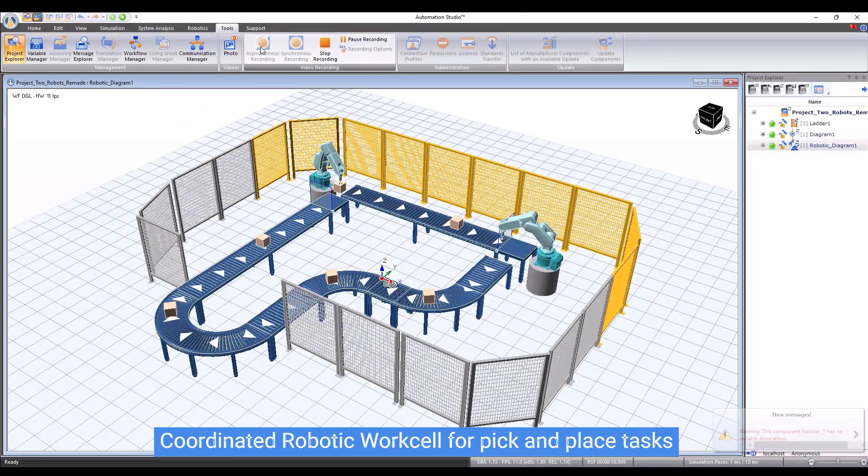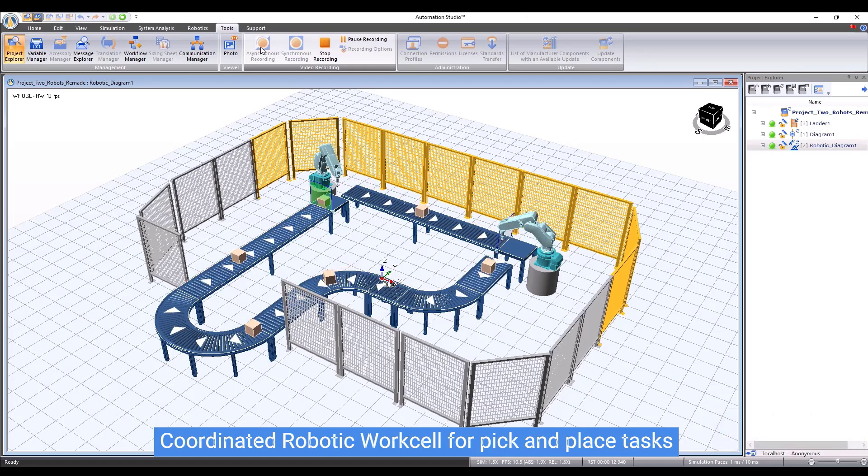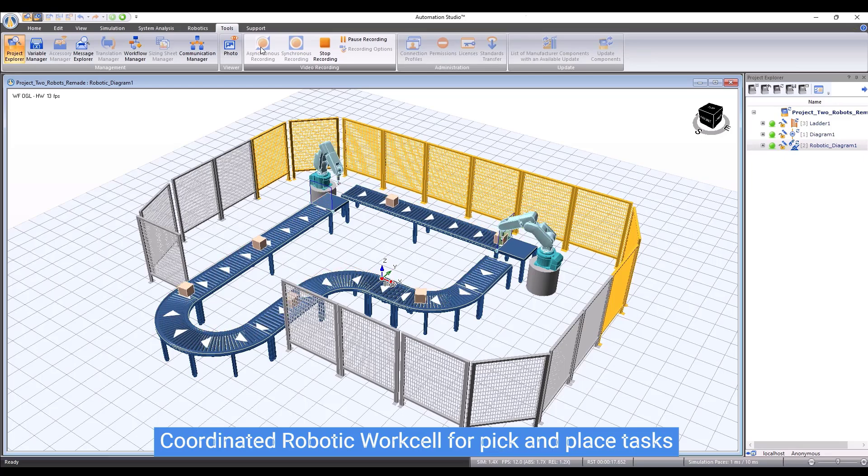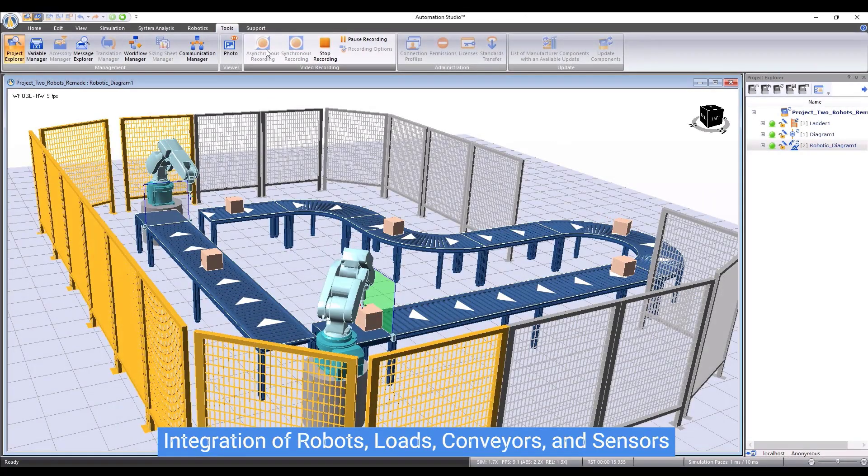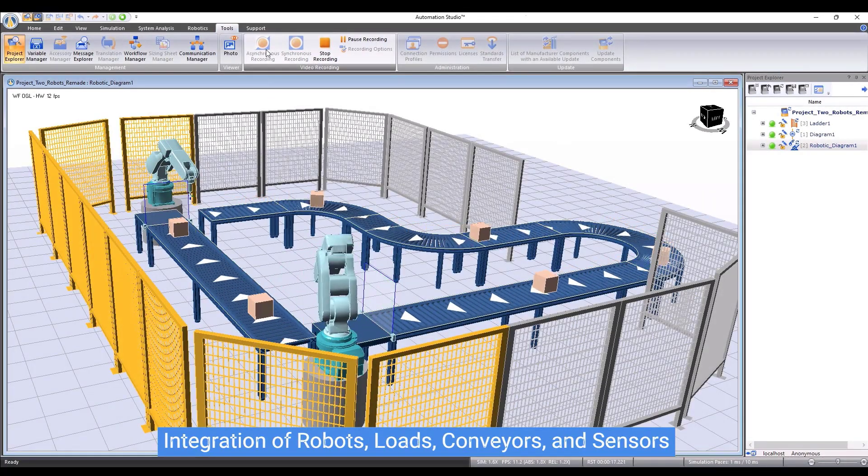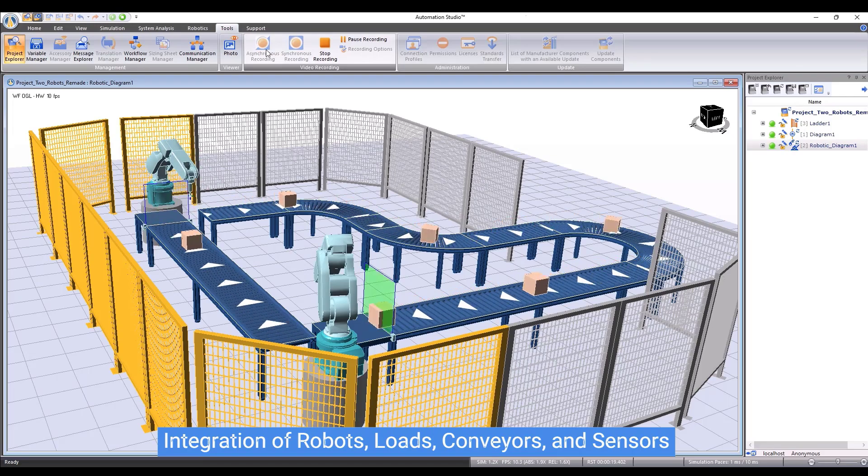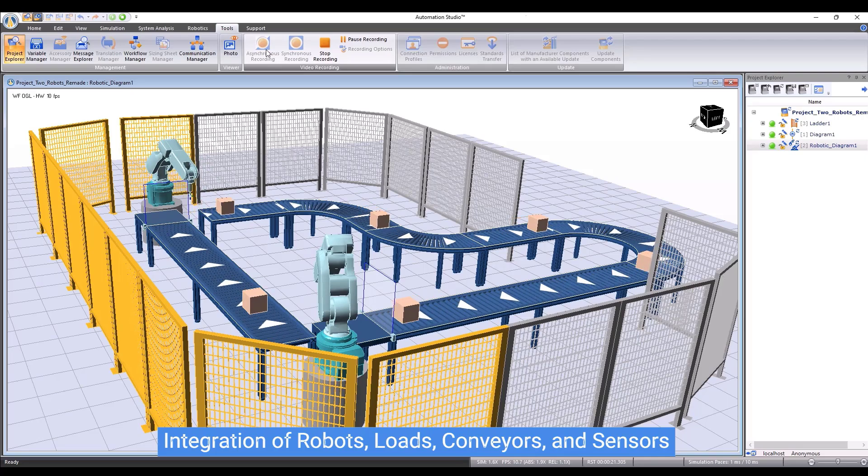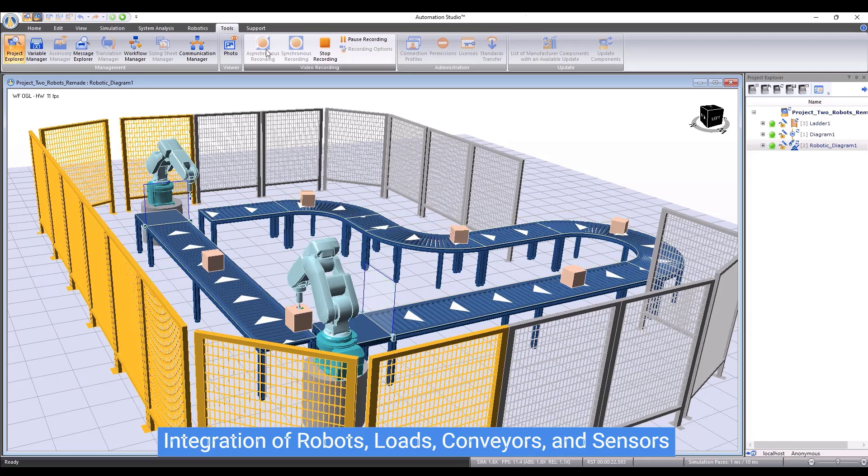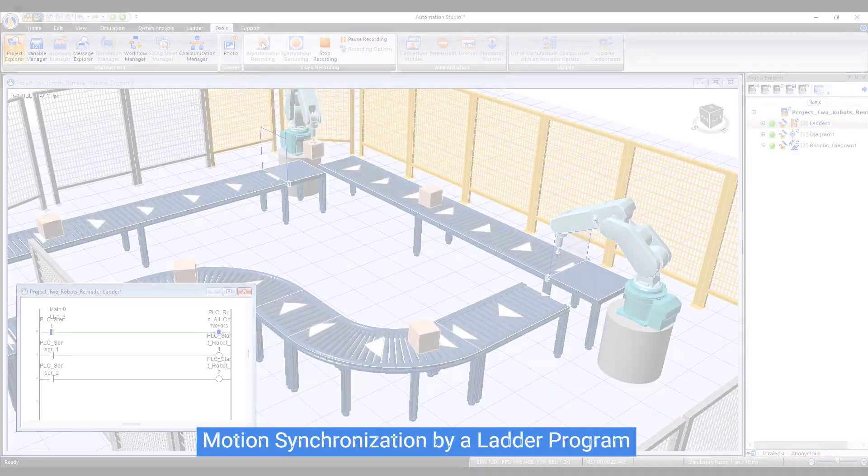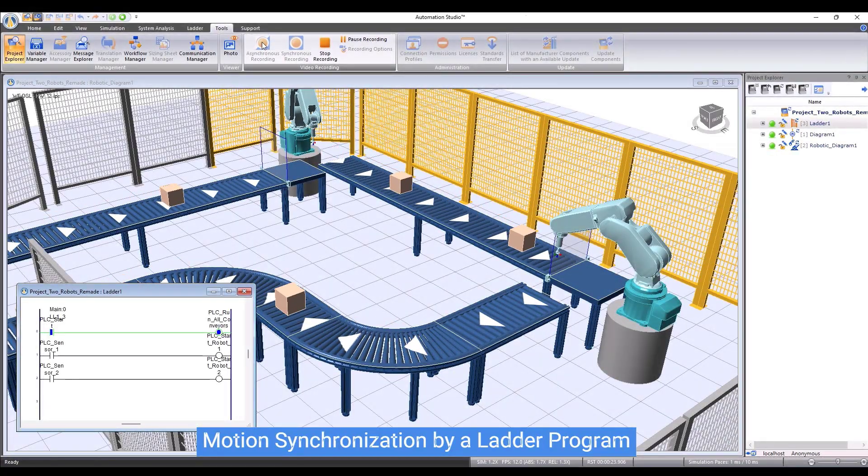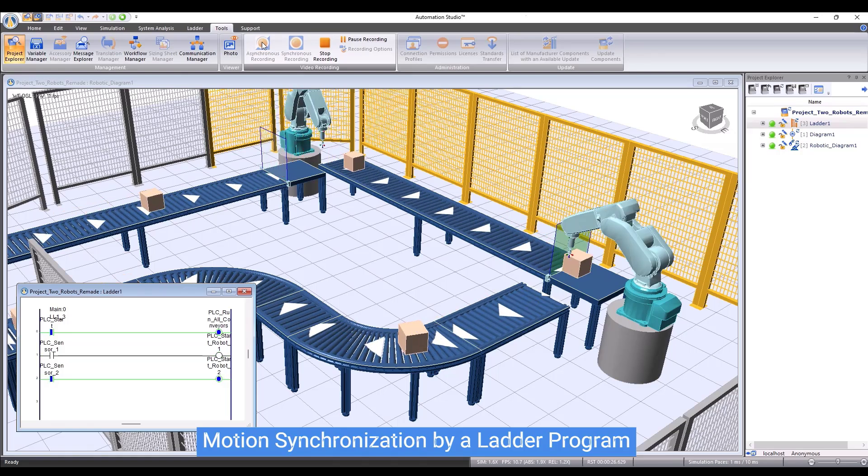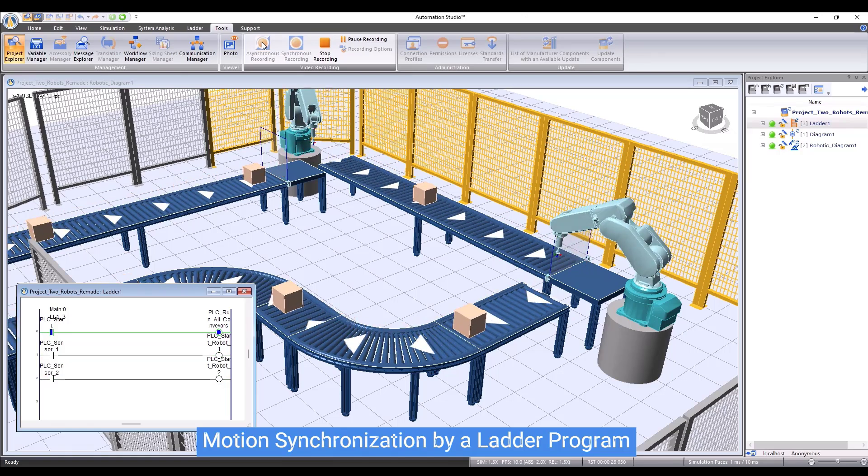Here is another example of workcell with multiple robots. This time we can see that there are two robots, a production line with many curved conveyors and linear conveyors, two sensors, and several loads. A PLC ladder program is used to monitor the states of the robots and the sensors to synchronize the motion. During the operations, the two sensors always update their status to the PLC. If a sensor detects the presence of an object at the end of a conveyor, the PLC will ask the robots to execute their motion programs, which will bring a load from one conveyor to another.